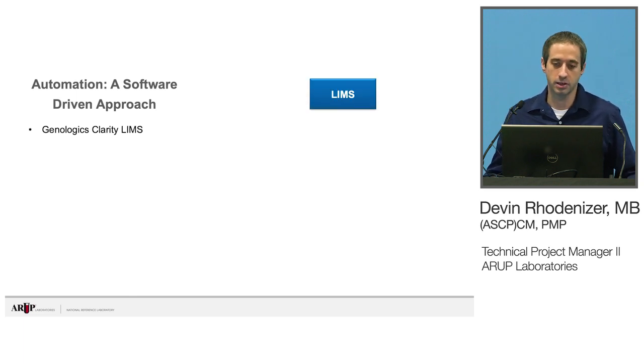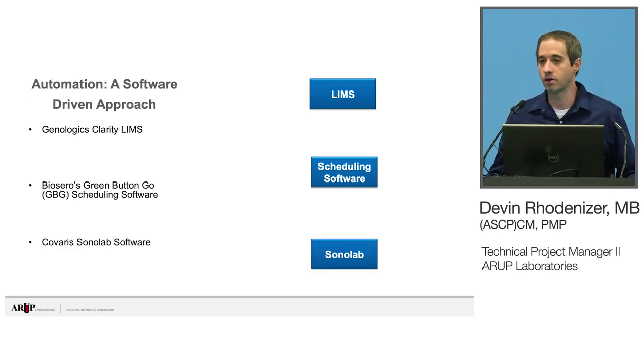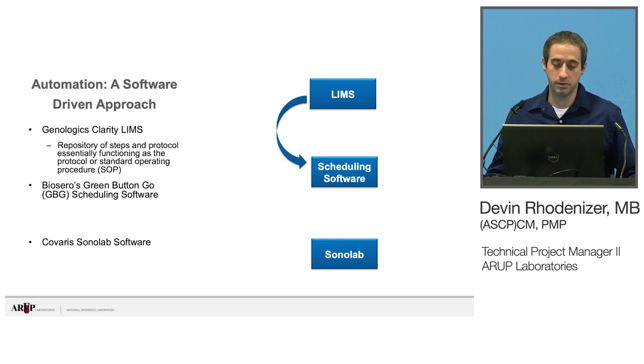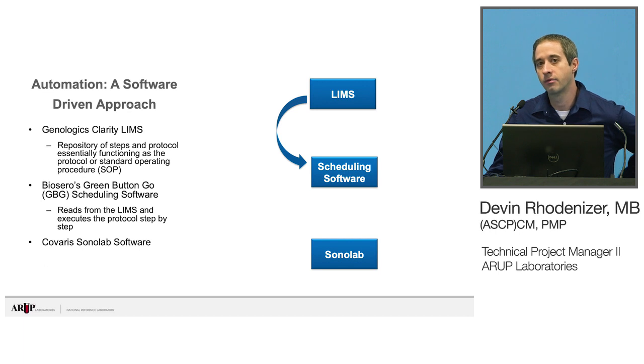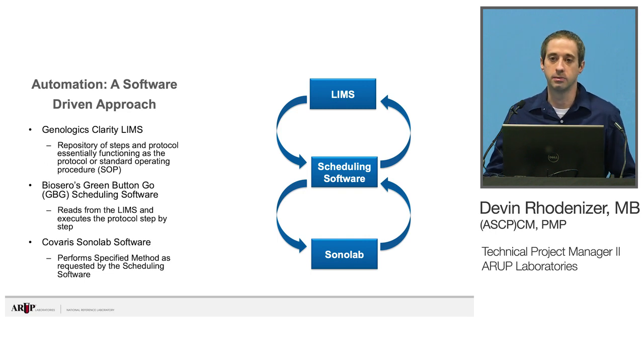A system like this involves a lot of software. We have Genologics Clarity LIMS — really three different parts of our software. We have the LIMS, we have the scheduling software utilizing BioSero's GBG or Green Button Go, and then the Covaris Sonolab instrument software. The LIMS is the repository of protocols and steps — it's really the lab's SOP down to a granular level, all the way down to moving into a centrifuge as a step. BioSero reads from the LIMS and executes the protocol, which allows a lot more flexibility so when things change, we only have to change one system. The Covaris Sonolab software executes the specified method requested by the scheduling software, and all information is passed back to the LIMS with log files kept as required by CAP and CLIA.